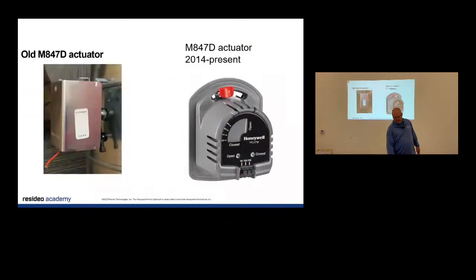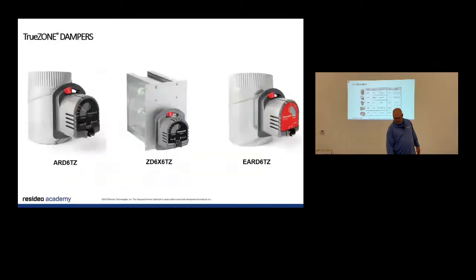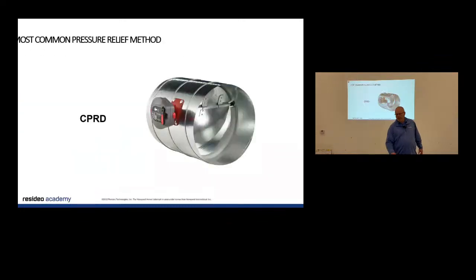So actually, yeah, it's on pressure of the system. And this is not electronic. Even though it's round, and there's a flapper or a damper in here, this device is just a spring inside a fancy looking cabinet. And that spring is basically holding that damper closed. And if that air has to bypass, that spring lets this open and I dump that back into the system. So that is the difference between ours and other brands.